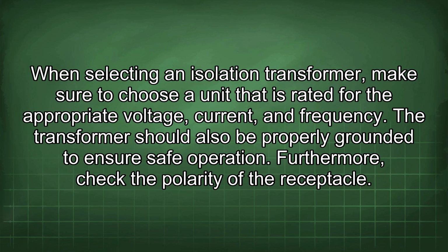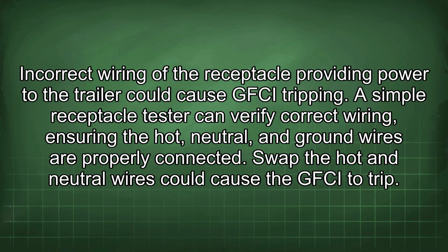When selecting an isolation transformer, make sure to choose a unit that is rated for the appropriate voltage, current, and frequency. The transformer should also be properly grounded to ensure safe operation. Furthermore, check the polarity of the receptacle. Incorrect wiring of the receptacle providing power to the trailer could cause GFCI tripping. A simple receptacle tester can verify correct wiring, ensuring the hot, neutral, and ground wires are properly connected. Swapping the hot and neutral wires could cause the GFCI to trip.